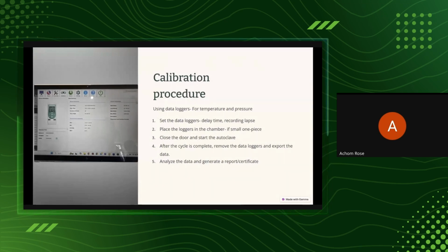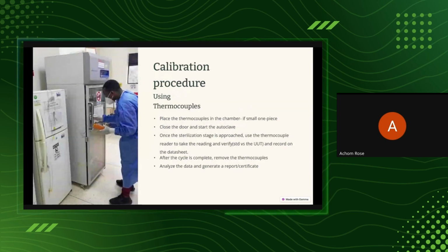If you're using the thermocouple, I had the picture for the autoclave, but it was not coming out clearly. So ignore, this is a fridge, but they have the same setup. But all I wanted is for us to see this. This is a thermocouple reader. So you place your thermocouples inside the chamber. There are some also which are hanging here. These are the thermocouples that we are talking about. So this tip, this head, the yellow one that you're seeing, is the one that we are going to place into the reader, and then we read. It is also the same.